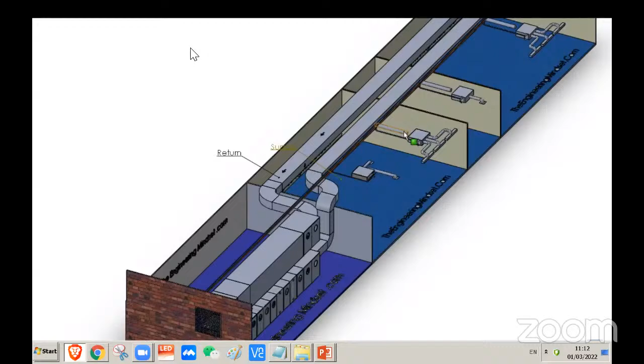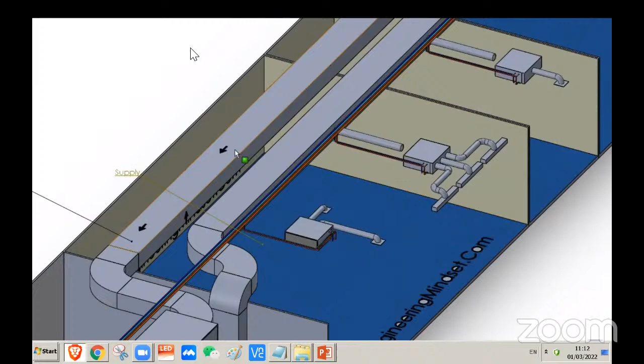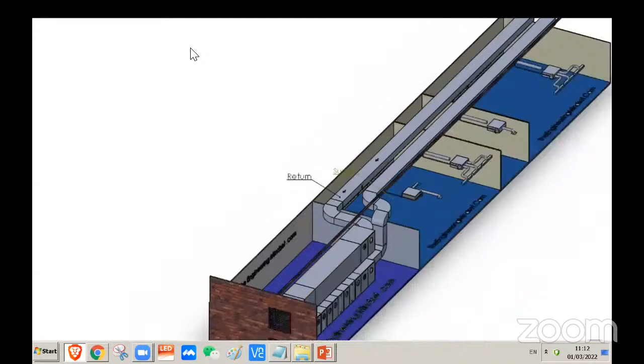So this fresh air is directed into the inlet of the fan coil unit, and it's usually not connected though. There's a gap in between. There is a reason for that, which we'll look at later. So that fresh air enters into the box. It gets sucked inside. Here's a fan. We'll have a look inside that shortly. And that air gets heated or cooled and pushed out through these diffusers into the space. Now some of that air will recirculate up through the false ceiling, through those grills we looked at, and back into this box here, whereas some of the air will be picked up into this return duct, and that will be sucked by a fan here and pushed out of the building.